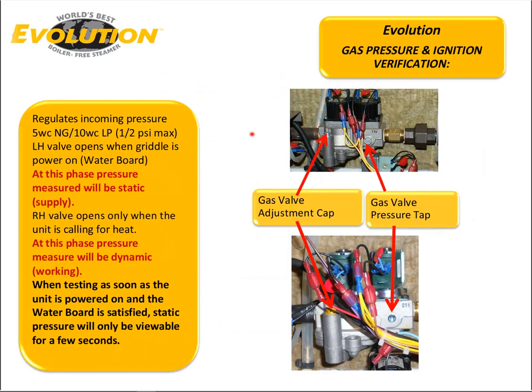So the first thing we'll discuss is the gas valve for the Evolution steamer. You'll notice there are two pictures here. We have recently updated our valve design. This is the old valve from 2018 backwards, and this is the design that we will be moving forwards. The valve body is very similar, just a difference in the coil and the coil wiring. As we discussed earlier, this valve is capable of regulating the gas pressure within the unit. If you know that the pressure supplied to the steamer is over 14 inches water column or a 1/2 pound PSI, do not hook the gas up to this unit beforehand. You will break those valves. So we need to keep it below a 1/2 pound PSI.